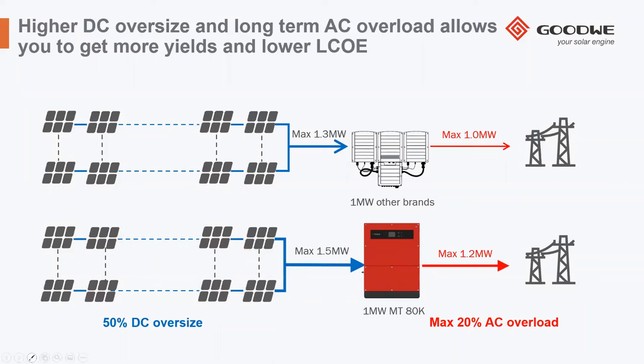So the capability to have up to 50% DC oversize means, as an example, that the MT80 can easily handle up to 120 kilowatt on the DC side of PV module. And you can get up to 96 kilowatt output on the AC side. It's clear that by playing with these two, and that these are granted without derating, you can easily design your system according to your local needs in terms of grid operator and in terms of climatic conditions.